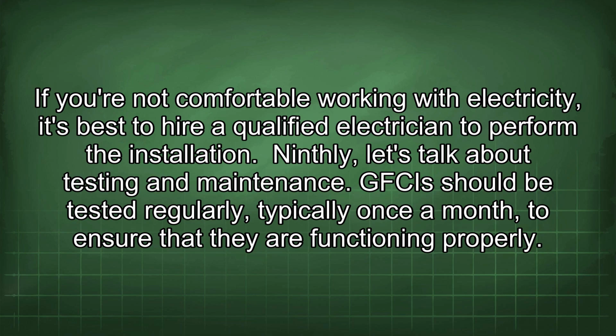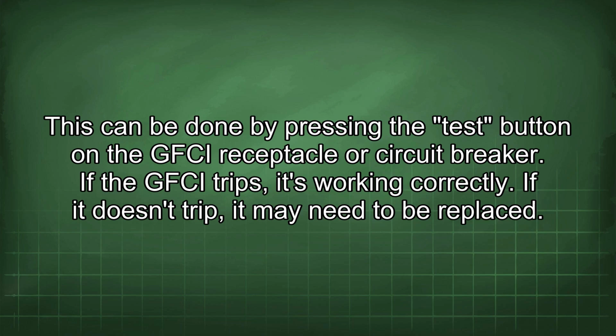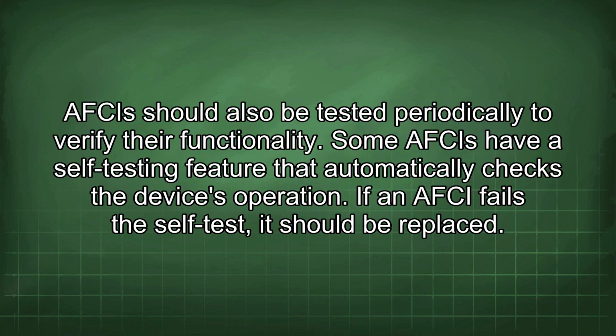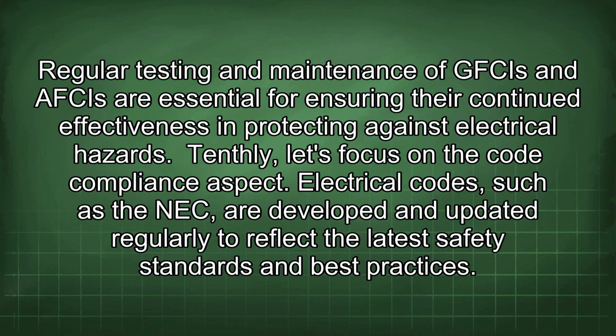Ninthly, let's talk about testing and maintenance. GFCIs should be tested regularly, typically once a month, to ensure that they are functioning properly. This can be done by pressing the test button on the GFCI receptacle or circuit breaker. If the GFCI trips, it's working correctly. If it doesn't trip, it may need to be replaced. AFCIs should also be tested periodically to verify their functionality. Some AFCIs have a self-testing feature that automatically checks the device's operation. If an AFCI fails the self-test, it should be replaced. Regular testing and maintenance of GFCIs and AFCIs are essential for ensuring their continued effectiveness in protecting against electrical hazards.